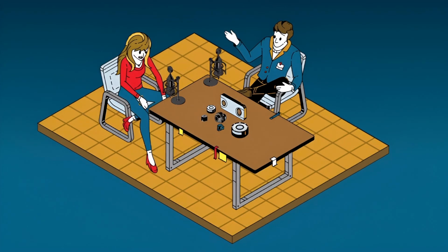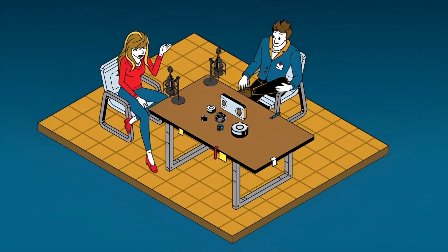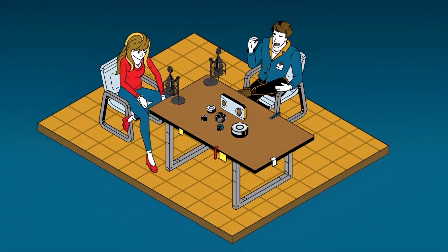Okay, that covers the physical side. Let's move to the environment, which I imagine works a bit more slowly but can be just as devastating. Oh, absolutely. Killer number 3. Moisture and corrosion. Water is just a nightmare for any electrical resistance device. In damp or wet environments, moisture gets in and causes internal corrosion or slow electrical shorts. And what does that do to the signal? Well, the corrosion changes the impedance of the electrical pathway. So you start getting unstable readings or maybe a continuous signal drift. It just goes haywire. So if you're installing a cell outdoors or in a washdown area, you have to be actively looking at that sensor's IP rating, the ingress protection rating. It's not a feature, it's a requirement. You cannot just assume the sealing is good enough.